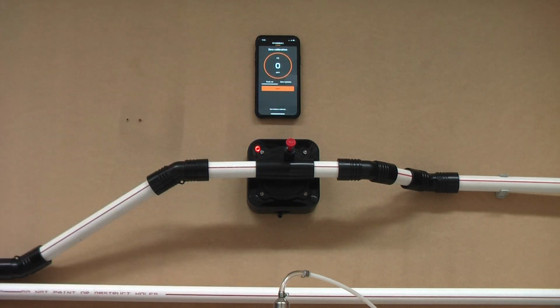The first stage of the calibration process will be to make sure that we're detecting 0 parts per million of gas when we're not applying gas to the detector. So to do this, I'll push the 0 button. The detector will now sample readings associated with this calibration data. This part of the test is now passed.